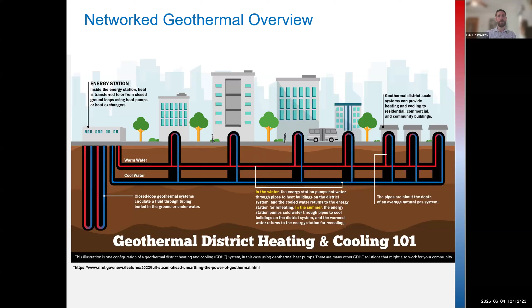The last piece of the picture here is the ground source heat pump. I'll talk a bit more about that in a few slides, but it's sort of the third leg of this stool in terms of providing heating and cooling to the buildings, because you can't heat very well with 55 or 60-degree water. You need to get it all the way up to 90 or 100 degrees to really properly condition the inside of a building.